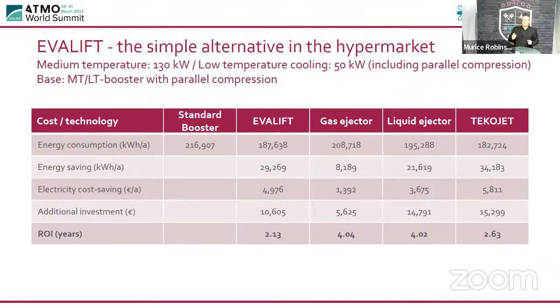But you can see at the bottom, when I have a look at the return on investment, I'm not going to go through all the other figures with you, but you can see the EVALIFT would take just over 2 years to pay itself off. Gas ejector was on 4 years. Liquid ejector was on 4 years, and the TEKO Jet was on 2.6 years. This is because of the difference in the additional investment. I'm not saying that EVALIFT doesn't outperform, because it normally does on larger systems compared to a gas and a liquid ejector. But you can see the payback period, because the simplicity is the main goal over here.